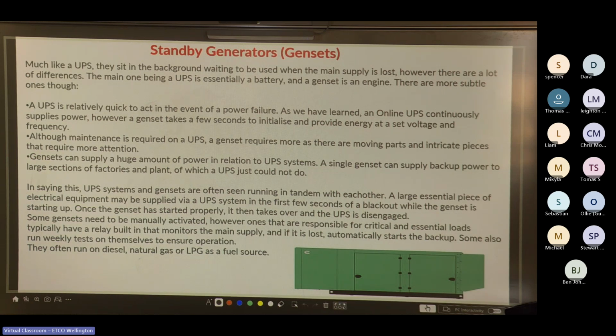Especially some of the bigger standby generators, they can leave them hooked up to the supply for days or weeks at a time, as long as you maintain the fuel level inside that genset. A UPS system and genset are often seen running in tandem. A large essential piece of electrical equipment may be supplied by a UPS in the first few seconds of a blackout while the genset is starting up, and then once the genset is started properly, it takes over and the UPS is disengaged.